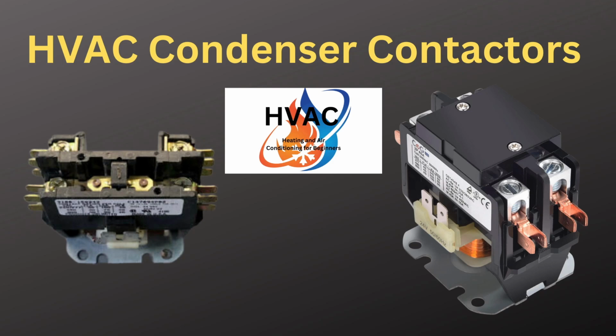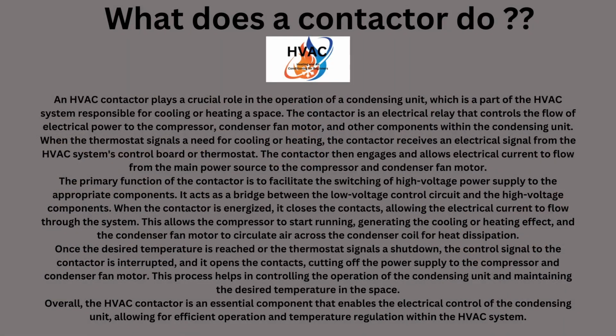Now, we're going to go over what the contactor actually does. What is its actual job? And also, how long of a lifespan does a contactor actually have? But first, let's go over what a contactor does. An HVAC contactor plays a crucial role in the operation of your condensing unit, which is the part of the HVAC system responsible for cooling or heating a space. A contactor is an electrical relay that controls the flow of electrical power to the compressor, condenser fan motor, and other components within the condensing unit.